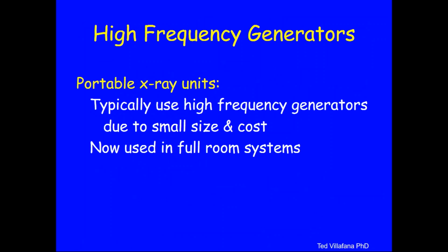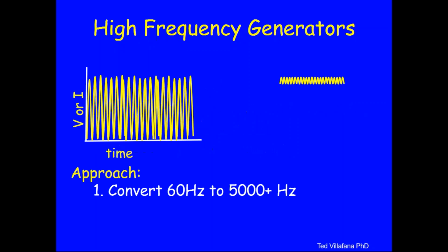High frequency generators. This is becoming more and more popular, these types of generators, but I'm going to back up to portables and then build up to the high frequency generators. A typical portable machine is a high frequency generator. Let's see what we mean by that. Remember that portables are relatively small units. So you want a system that is relatively small that you can roll around the hospital. And the way they accomplish that is with a high frequency generator. And let's take a look at that.